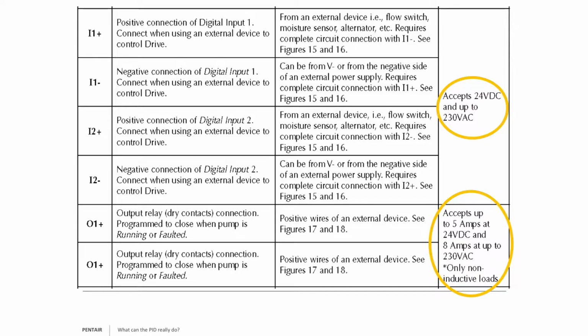Outputs. Output is just a dry contact. It's going to close upon a command. So inputs, what I like to tell people is an input tells the VFD to do something. An output, the relay will close because it's communicating what the drive is doing based upon what you asked it to monitor.